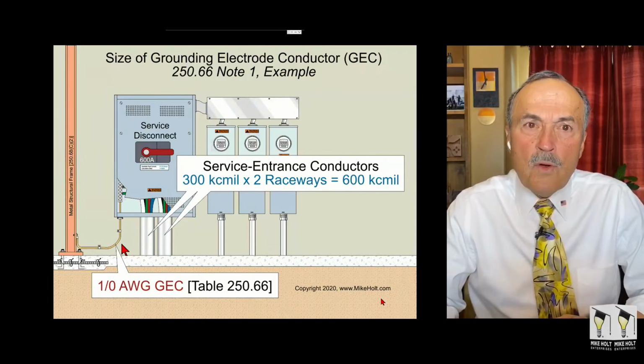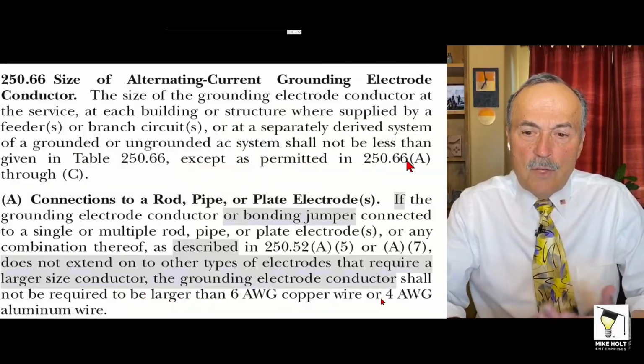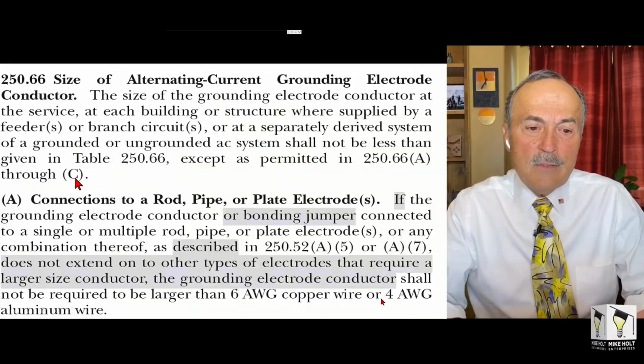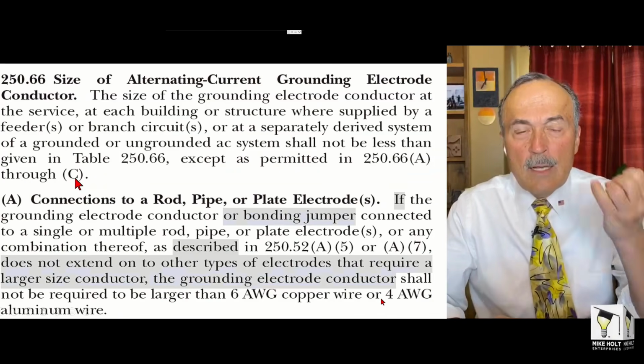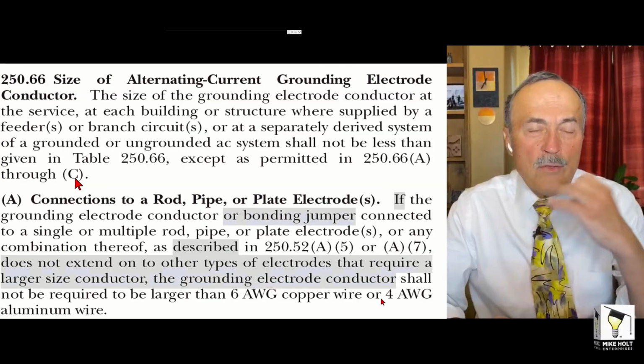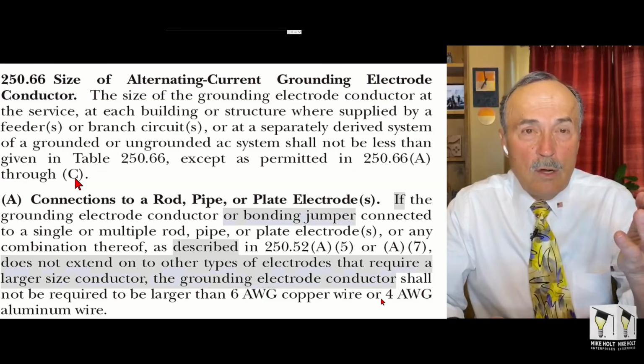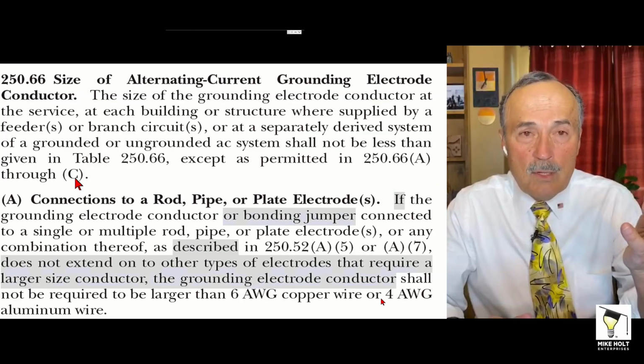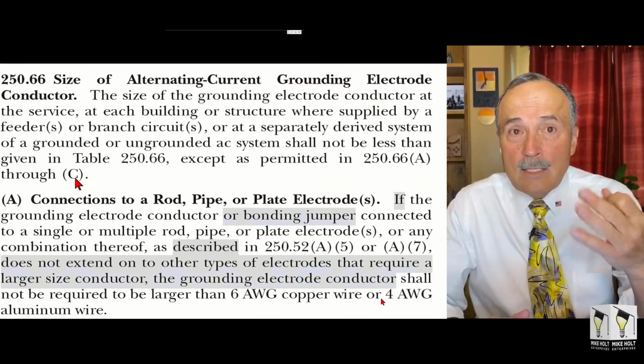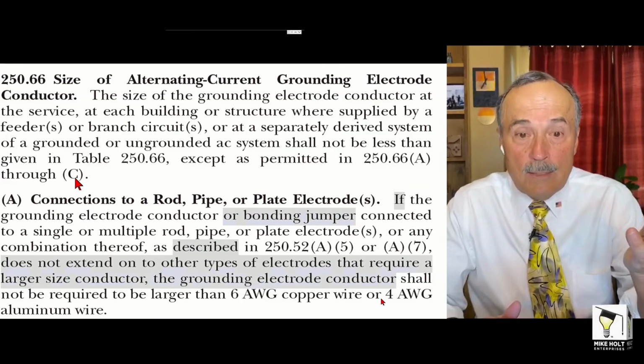Then what's the table for, Mike? Well, the table is if you don't comply with 250.66 A through C. A is a ground rod, B is a concrete encased electrode, C is a ring around a building, which is stupid. Hopefully nobody does that. But if they put a ring around a building, then whatever the size the ring is, that's the size wire you have to run to the grounding ring. Okay?